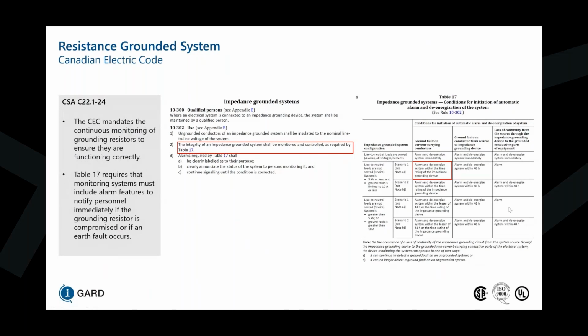And then the third column is in relation to an open circuit, where we now have an ungrounded system. On the left-hand side, in the impedance grounding system configurations, we have a stipulation for line-to-neutral loads being served with a fourth wire being distributed throughout the system. And in this case, for each of the 3 conditions, it says alarm and de-energize the system immediately.